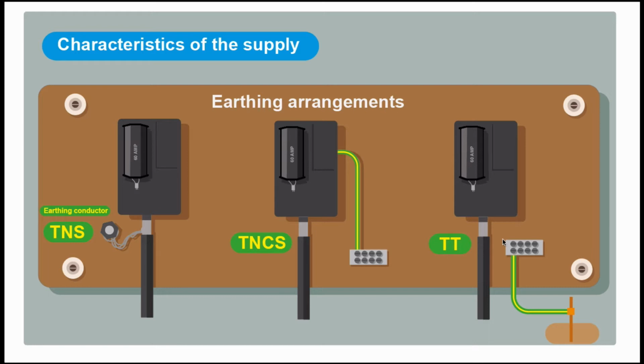We also have a TT system. This is where an earth is not supplied. We have to supply our own earth. This is generally via a rod in the ground. We bring the conductor into the house and connect it to the main earthing terminal, where all our CPCs and all of the earthing connections go on to.